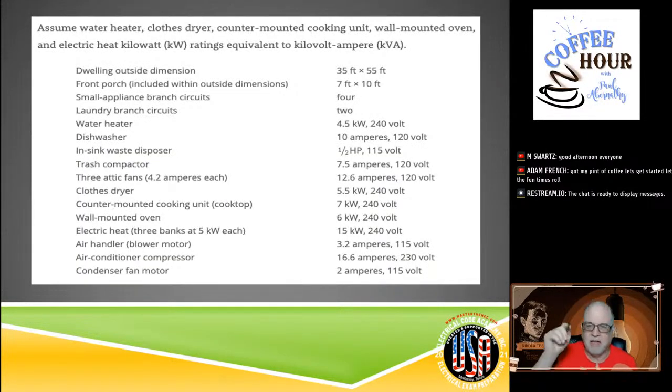All right, back to our question. So now we've knocked off the first 1, 2, 3, 4. Now we're getting down to the appliances. So if you're taking an exam and they want to know the general lighting, and they want to know what the calculated load is versus what the connected load is, or what the demand factors applied, then remember, if it's just the connected load, you take full values. If it's the calculated load, that assumes that you're going to have to apply something. And so, like if you were doing an exam and they wanted to know after demands, what's the calculated load, and it tells you it's a small family dwelling, guess what? They've got to give you the dimensions. They're going to have to tell you how many small appliances there are if they expect you to do more than 2, because 2 is the minimum. And then you know you have to have at least 1 laundry. But if they give you more, remember, you have to add the VA for more when it comes to small appliance and laundry. So just things to think about.